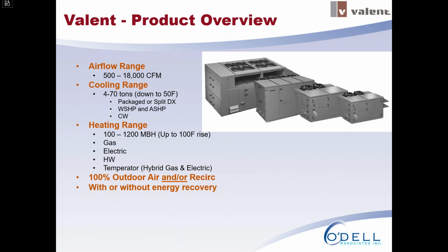So the electric on those temperators is actually sized to match the electrical capacity of the cooling requirement on the unit as well. So it doesn't affect your overall electrical incoming load. All the units are either capable of 100% outside air or they also can have recirc and modulating recirc dampers on them. So we can meet a very wide range of applications with a single box. And they also come, as Brian had mentioned, with or without energy recovery to create a more efficient solution.